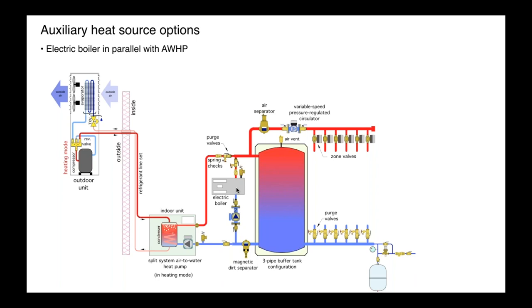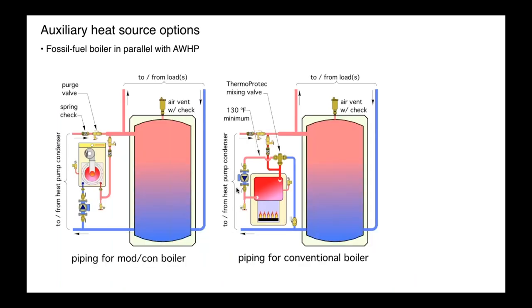So if the heat pump is out of service for some reason, the electric boiler simply takes over. Fossil fuel boilers, I think these are possible retrofit details. You probably aren't going to find today, with where trends are, where people are going to elect to go, an electric heat pump and also a propane boiler, because again, the carbon footprint. So in a retrofit situation, if there's an existing mod con, it can be piped just like the electric boiler.